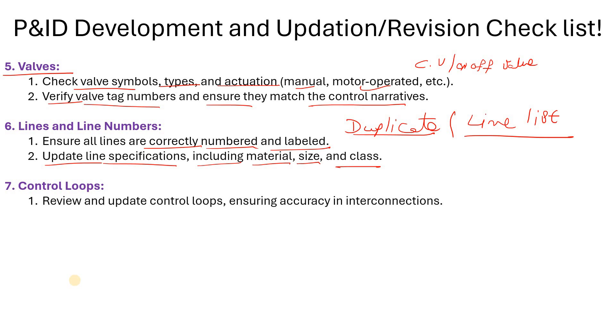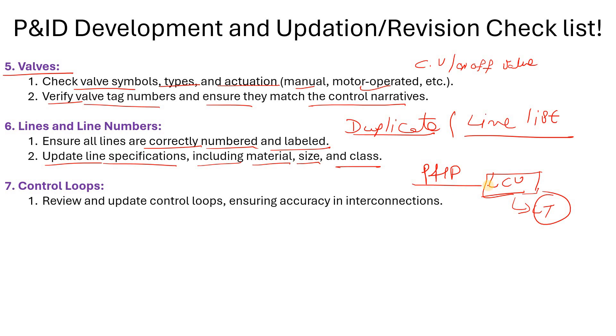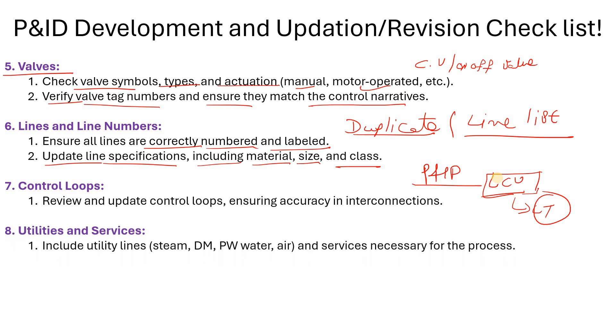Then the control loops — this point is also very important. If there is a level control valve, you need to show which LT it is connected to in the P&ID. Same for a flow control valve — with which FT it is controlling. And if there is a temperature control valve — with which TT it is controlling. These points are important and must be implemented in the P&ID.